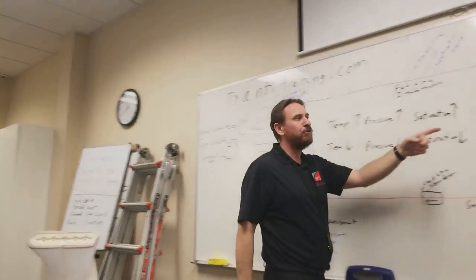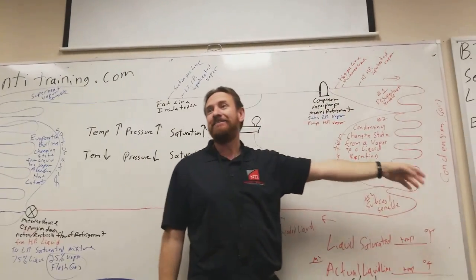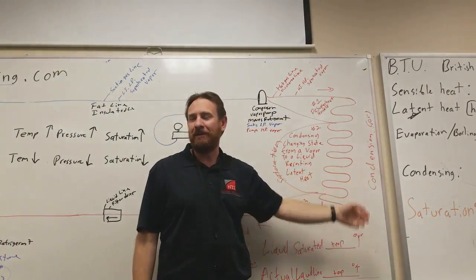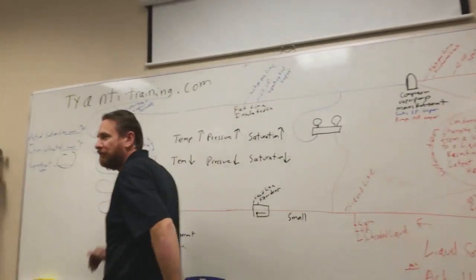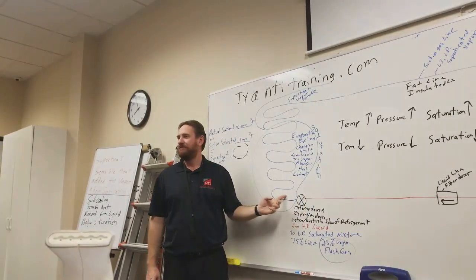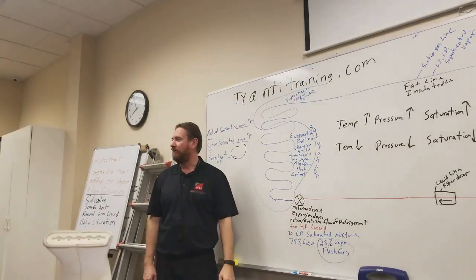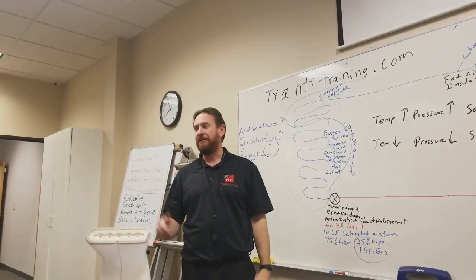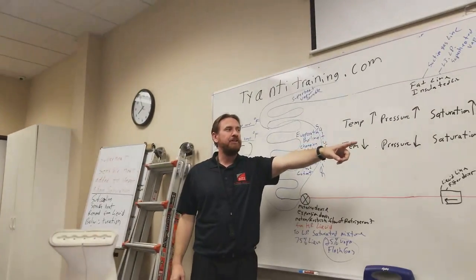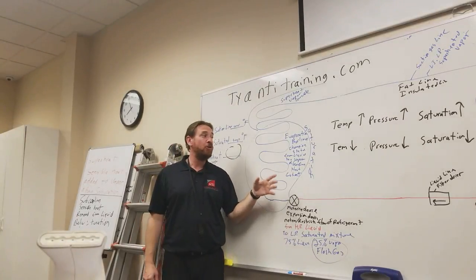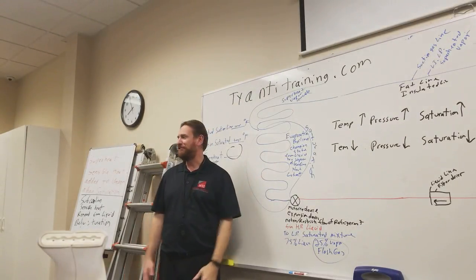Now, as my outdoor temperature starts to drop, like at night, what's happening to the pressure here? It's dropping. Now I have less push through this hole. Does that have an effect on this side? Yes, I'll have less pressure on this side as well. Less refrigerant coming through. We're going to be revisiting this thought process later. So the outdoor temperature affects the outdoor pressure, which affects how much refrigerant is coming through this metering device, which will have an effect on the indoor pressure.